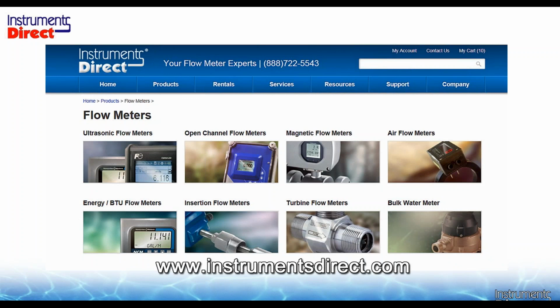So what did we learn today? We learned that the ModMag series has a variety of magnetic flow meters there. It has some basic requirements like most flow meters there. A little neat thing about the mag meter is it doesn't need the traditional straight run of pipes that most other flow meters require. 3 and 2 is pretty much the standard for most elbow-to-elbow applications there.